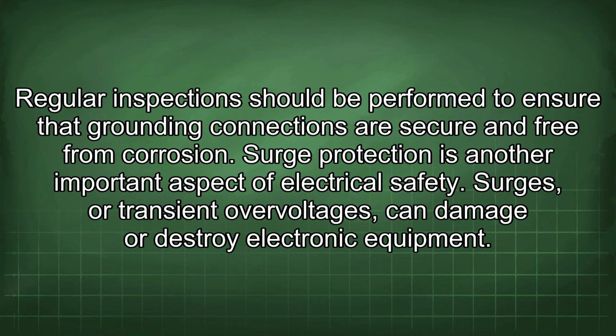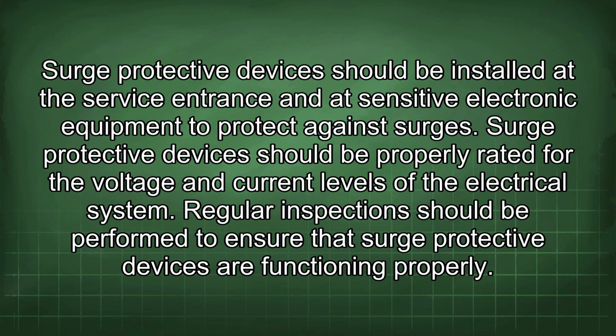Surge protection is another important aspect of electrical safety. Surges or transient overvoltages can damage or destroy electronic equipment. Surge protective devices should be installed at the service entrance and at sensitive electronic equipment to protect against surges. Surge protective devices should be properly rated for the voltage and current levels of the electrical system. Regular inspections should be performed to ensure that surge protective devices are functioning properly.